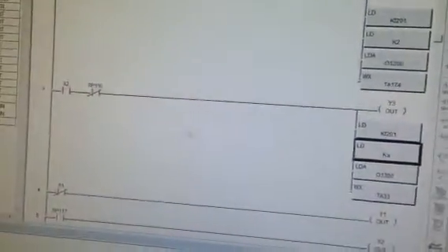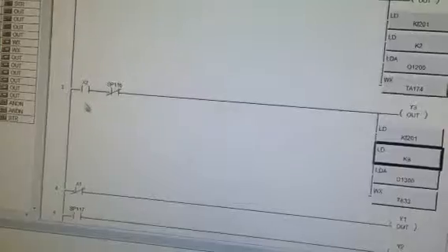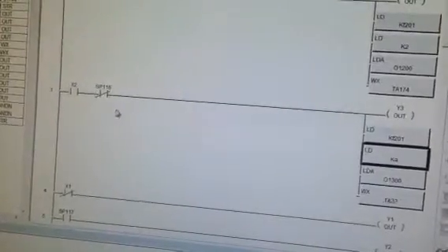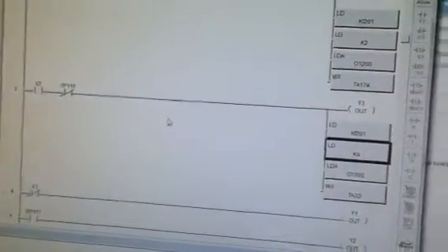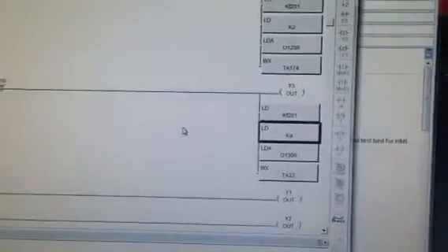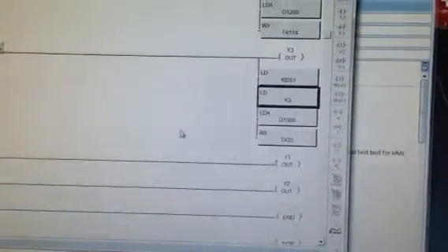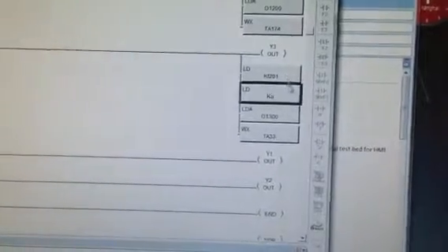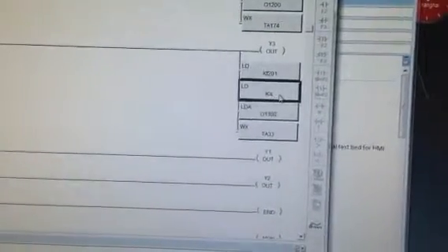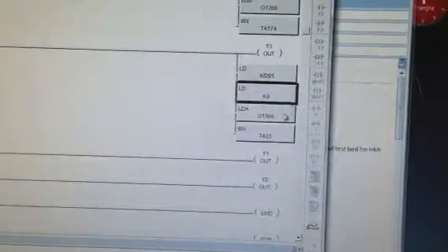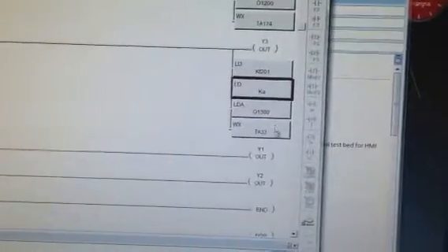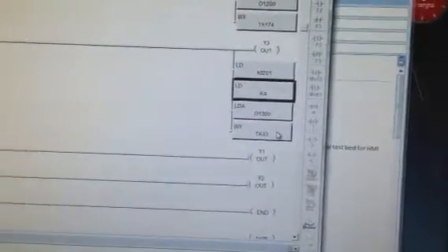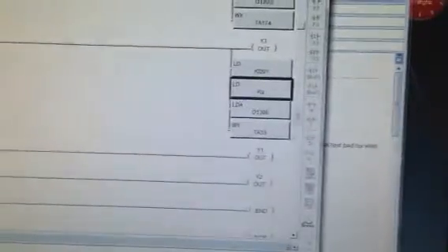Okay, next, when I press the button connected to input X2, and again when the Modbus channel is not already busy, we will do a block transfer, and again we're doing Modbus to slave address 1. A hex means we want to transfer 10 bytes starting at 1300 and going to address 33, which is really 40028, and that's going to transfer all the move parameters to the drive.